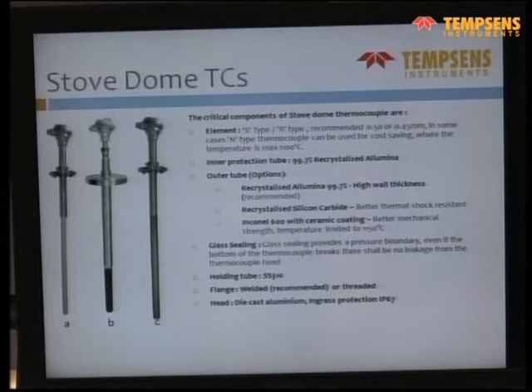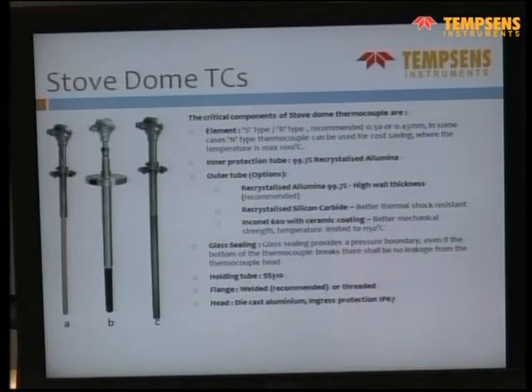So we have this application in which there are three solutions. The first one is with double ceramic protection. Inside is an S-type or R-type thermocouple, and there are two layers of ceramic, and outside the holding tube. The second solution has silicon carbide outside and ceramic alumina insulation inside, and the third one has Inconel outer and inside is again alumina. As I told you earlier, for all R-type, S-type or B-type thermocouples, you need to have a layer of ceramic so that it is protected from the outside environment.